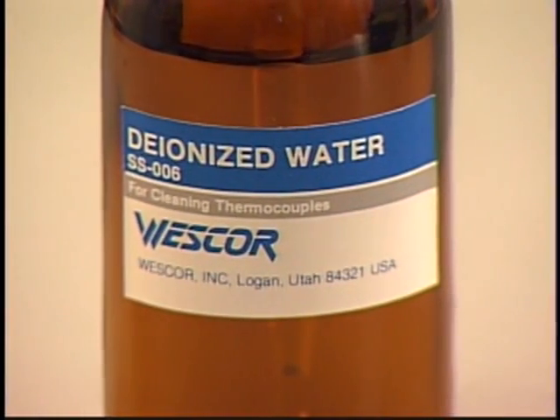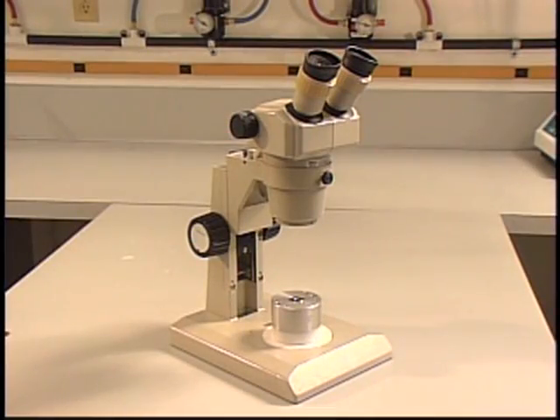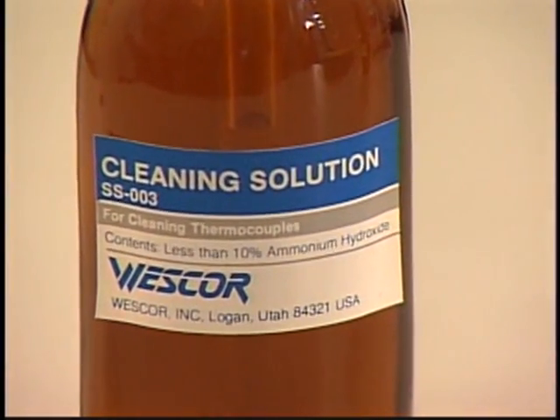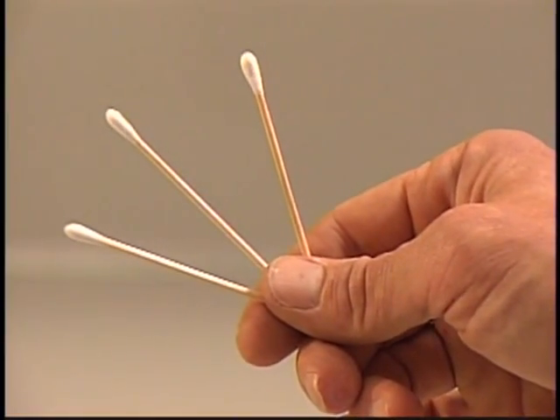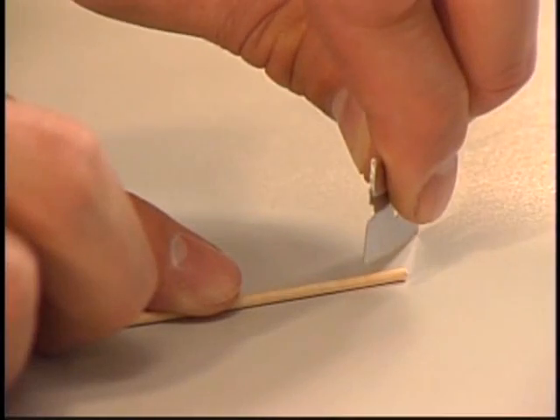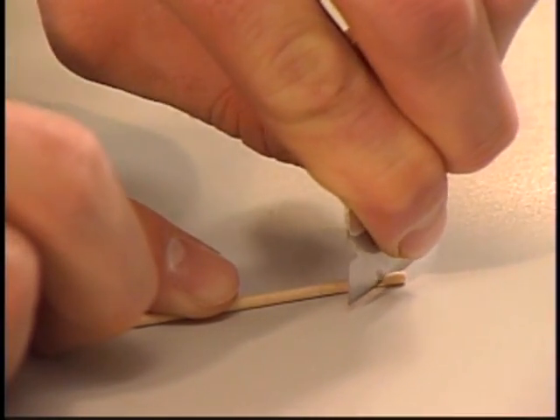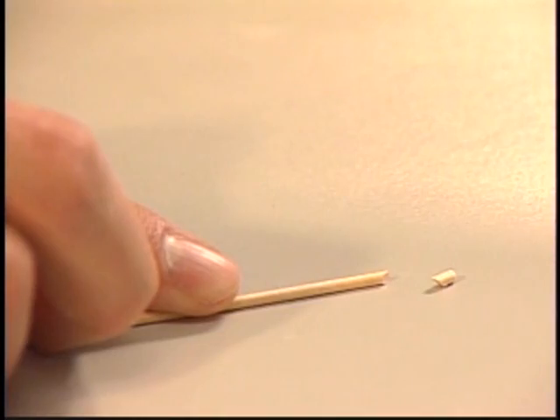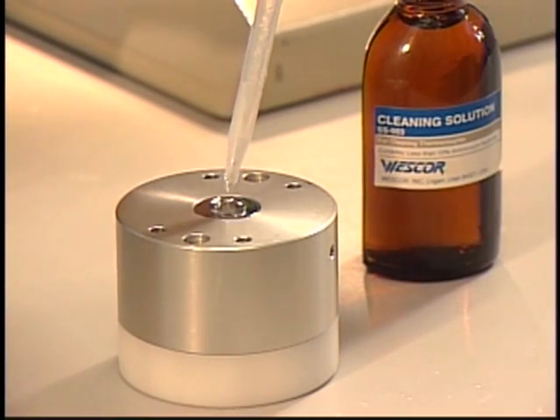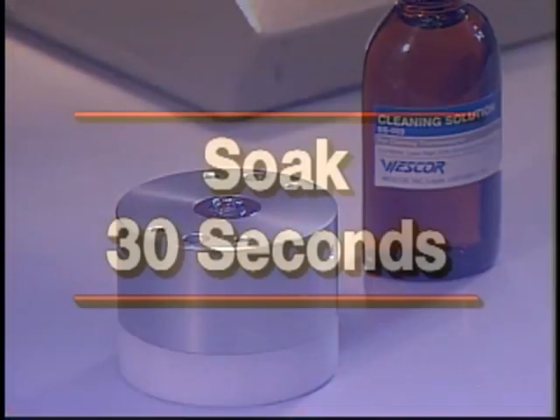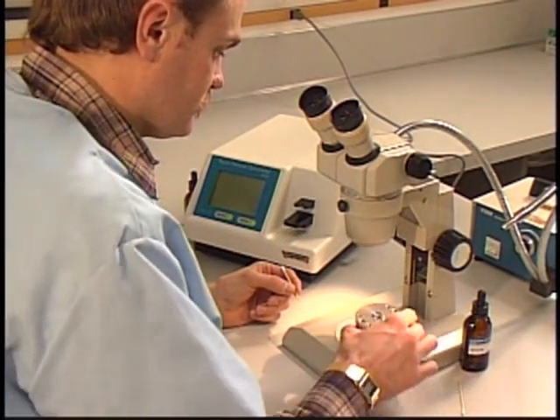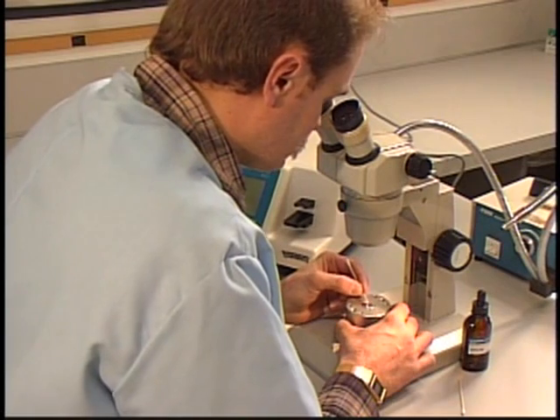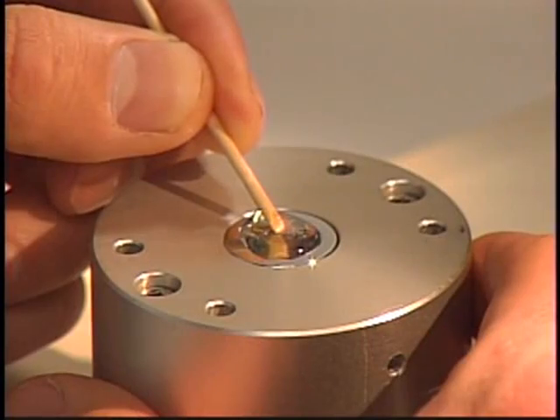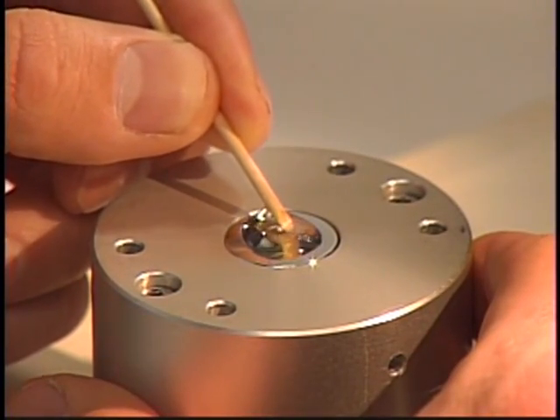For this battle, you need deionized water, a microscope, Wescor cleaning solution, and 3 swabs. Cut swab number 1 like so. This is your major weapon. Put 2 or 3 drops of Wescor cleaning solution on the thermocouple and let it soak for 30 seconds. Then very carefully take the pointed end of your finely crafted thermocouple gunk remover and clean under a microscope.